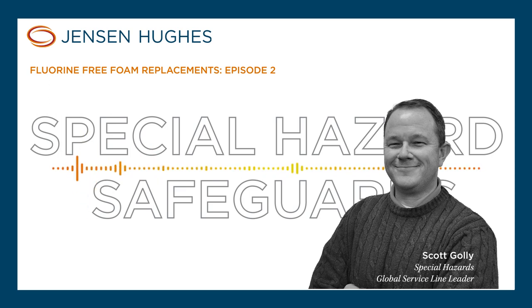Something to remember is fluorine-free foams are not film-forming. They don't produce that surfactant seal on the fuel, so aspiration becomes very critical. The NFPA Research Foundation produced a document called 'Foam Quality as Primary Driver for F3 Performance,' done by Jerry Back. Commercial F3 products use fluorine-free hydrocarbon or sulfonated surfactants, as well as solvents, stabilizers, and thickeners, which dramatically increase the viscosity of the F3 concentrate.